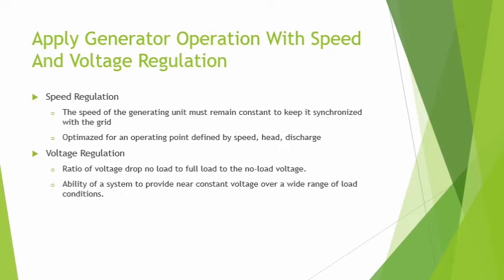Voltage regulation. Voltage regulation is the ratio of voltage drop from no load to full load to the no-load voltage. Full load means the point at which the transformer is operating at maximum permissible secondary current.